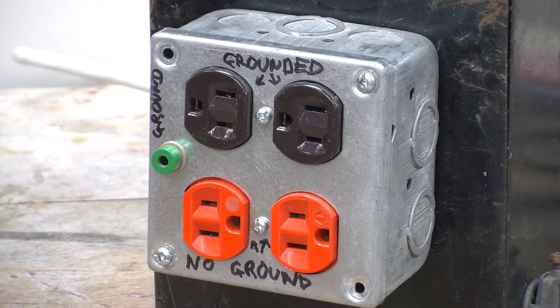Now, you might have noticed on both these devices, I have both orange and conventionally colored sockets. And you might be wondering why that is. And the reason I've done that is because these orange sockets have isolated grounds, which are normally used to take a separate isolated ground wire right to the electrical panel without attaching to any other ground wires. And that can be both for safety in settings like hospitals or for electrical noise in places like recording studios.